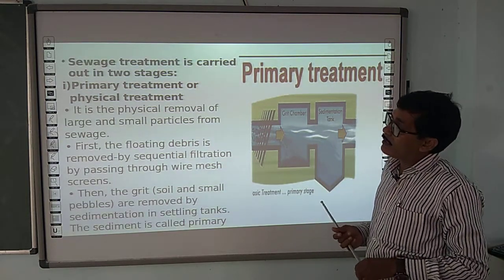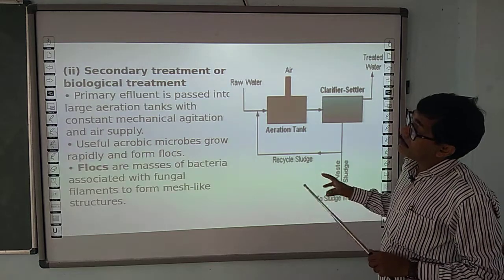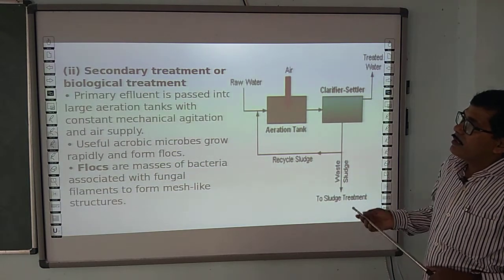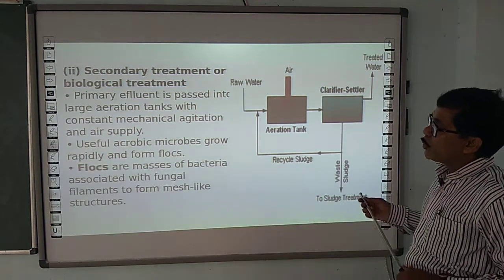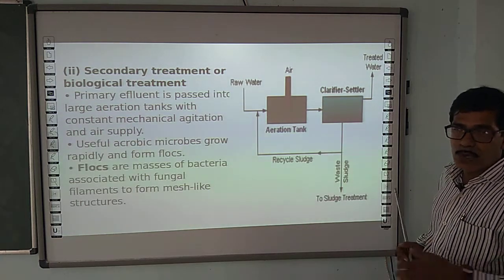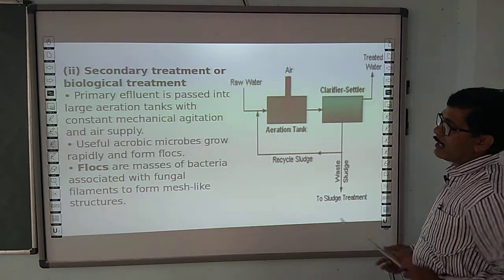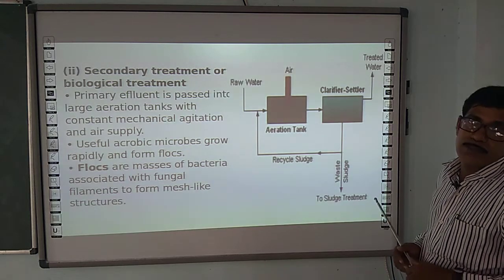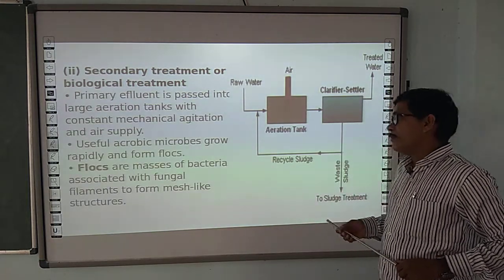Now we have secondary treatment. In secondary treatment, the primary effluent is passed into a large aeration tank with constant mechanical agitation and air supply, where useful aerobic bacteria grow rapidly. After growing, flocs are formed. Flocs are masses of bacteria associated with fungal filaments that form a mesh-like structure.